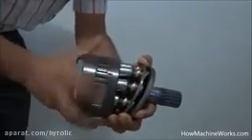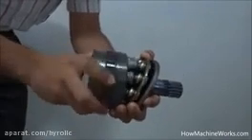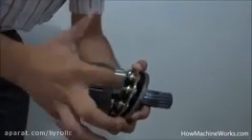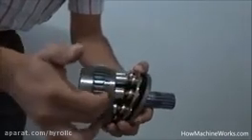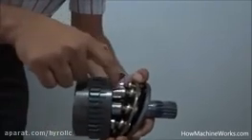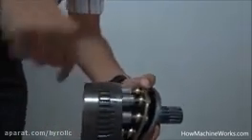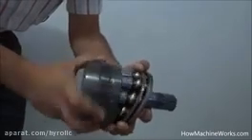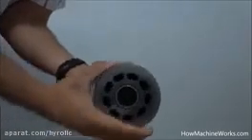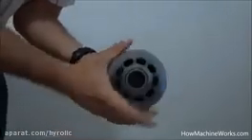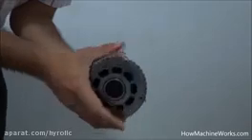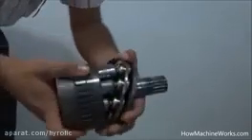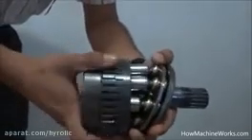So here you can see how the pistons actually move as the cylinder rotates. Both the drive shaft and the cylinder are rotating. At the bottom, the piston is moving back, which is creating a suction, and moving towards the top, the piston actually reaches the maximum suction, and as it rotates to the side downwards, the delivery is happening. You can see the piston movement inside the port of the cylinders very clearly over there. Have a closer look, and that's how it exactly works.